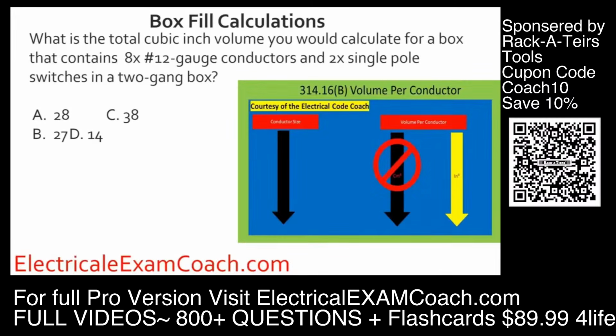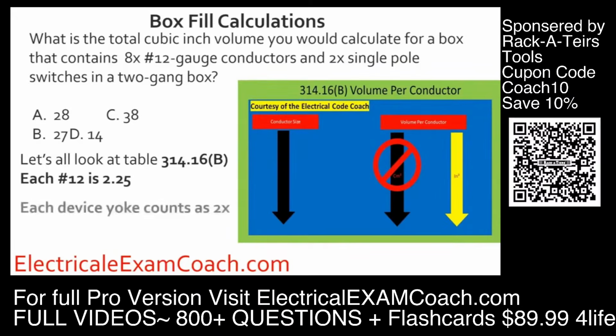What is the total cubic inch volume you would calculate for a box that contains 8 number 12 gauge conductors and 2 single pole switches in a 2 gang box? We look at 314.16(B). We know that each number 12 is 2.25. Let's go ahead and count our conductors. Each device yoke counts as 2 based off of whatever wire is terminating to the device.